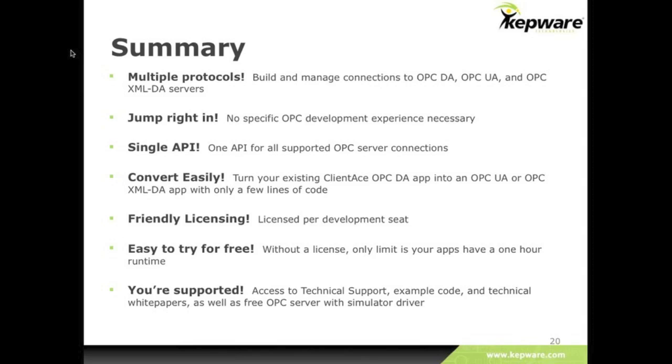So we have a question. How is fault tolerance in ClientAce? Yeah, so fault tolerance in ClientAce is really limited by the kinds of protocols that ClientAce uses. So OPC DA, there's not really a great fault tolerance solution for that protocol, right? It's up to third-party products to provide that fault tolerance. So we have a third-party product that does it. Other folks have third-party products that do it. Just because I have to mention, Kepware's redundancy master from us, that's what you'd use to provide failover between different OPC DA servers.